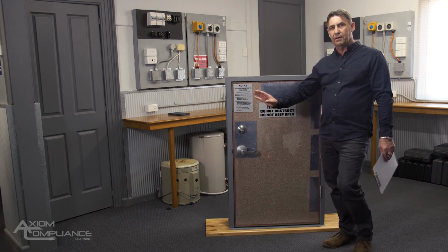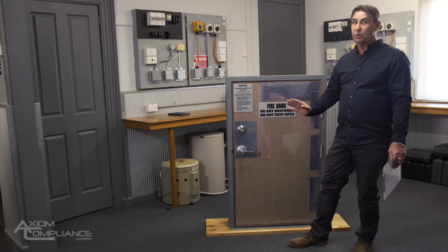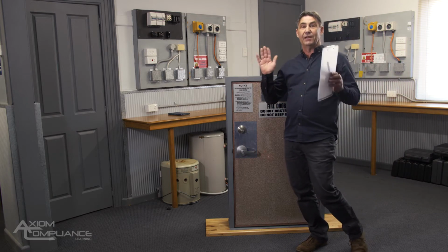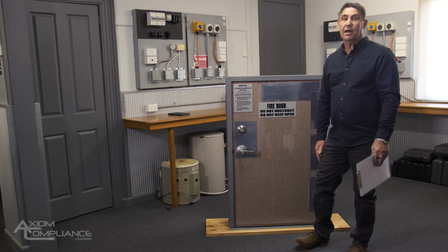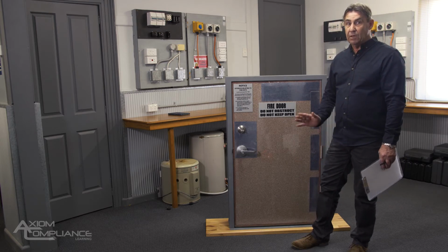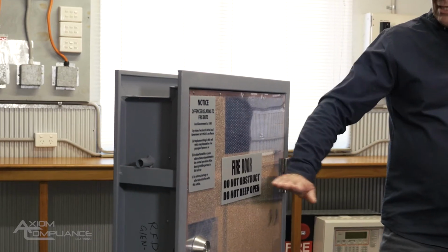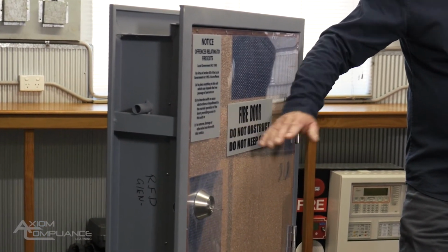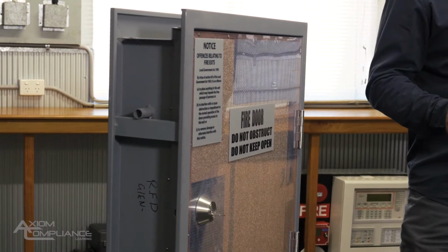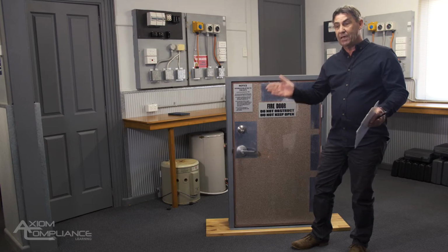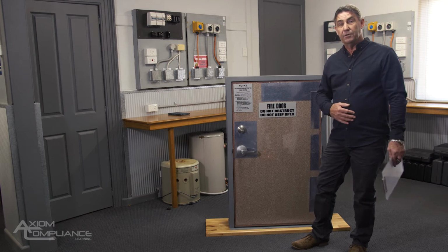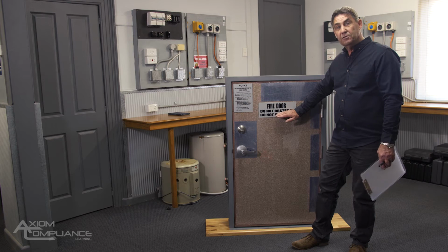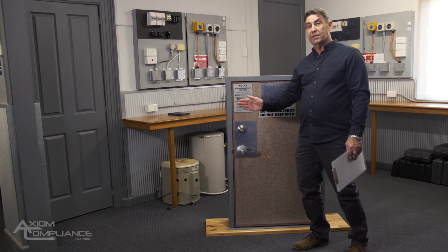So I'm just going to explain briefly what the signage should look like if you have a door egressing out into an open space where it's the last door somebody goes out of to get out of a building. So in that case, you must have this sign on both sides of the door. So that kind of indicates that we shouldn't be blocking the door, and the door shouldn't be kept jammed open at any point in time. So the fire door sign must be on both sides of the door when you're egressing into an open space.